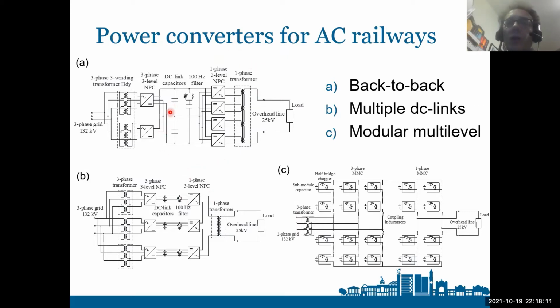The next topology is similar to this one, albeit with some differences, and is the multiple DC link topology. In this case each back-to-back converter is separated from the others, and they are parallel connected on the three-phase side and series connected on the single-phase side. The advantage of this topology is that the voltage on the single-phase side before the transformer can be increased by adding more modules. And also the waveform here is a sort of multi-level waveform. So by adding a sufficient number of modules, it's even possible to remove completely the single-phase transformer at the output in here.